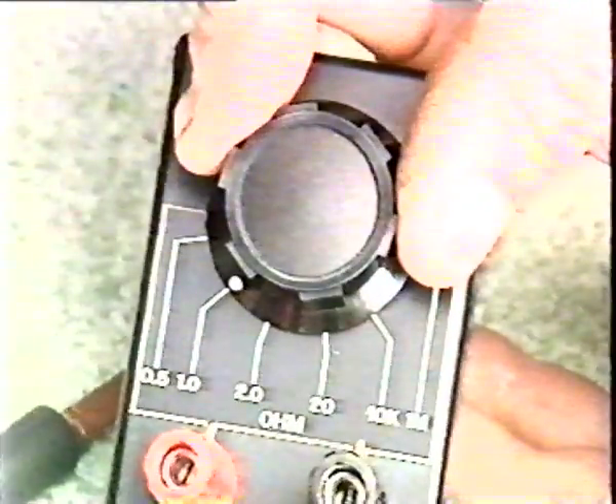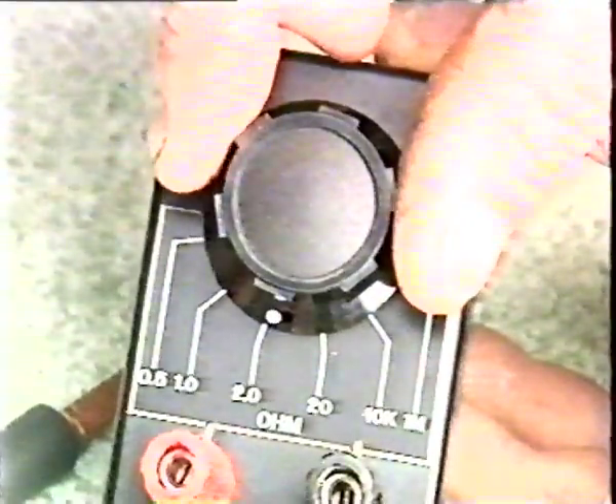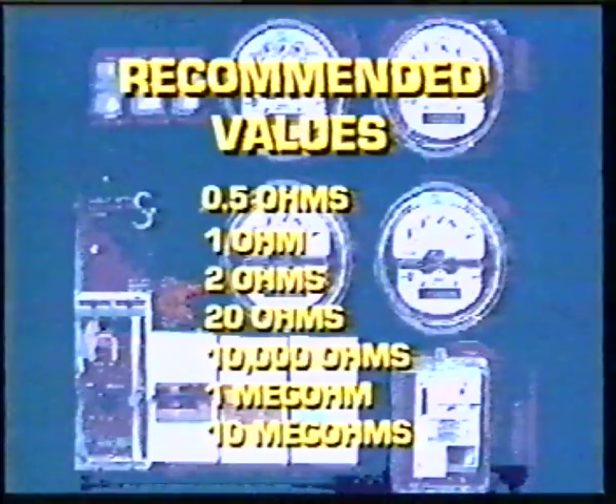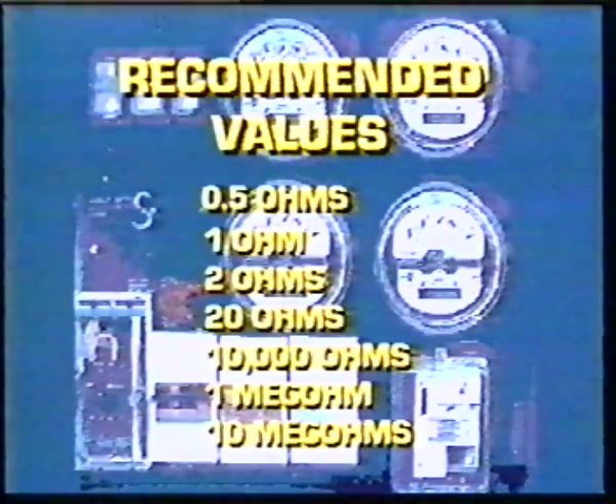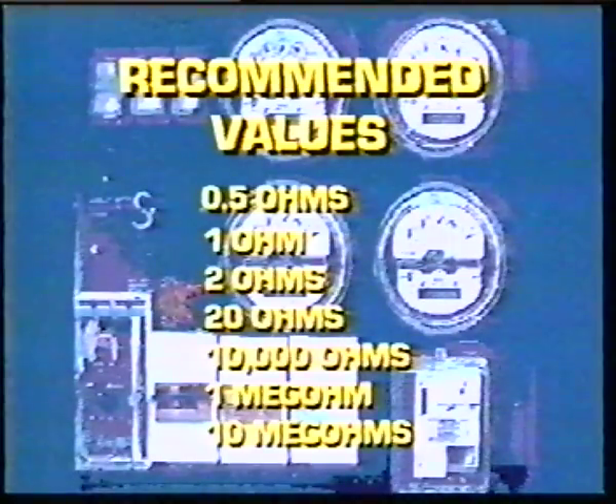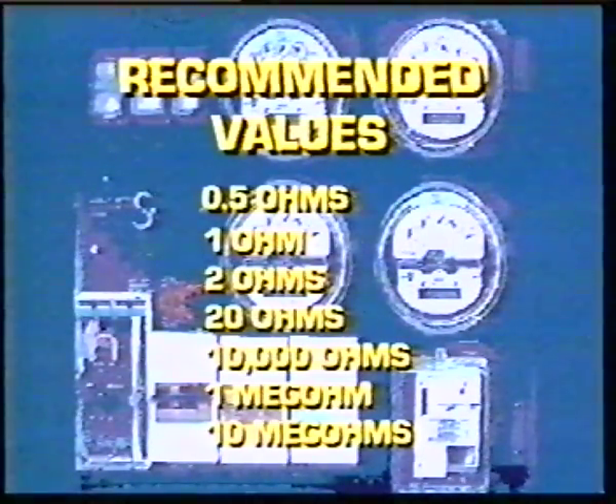In the case of the insulation resistance tester, it must be capable of maintaining its rated output voltage when testing a circuit or equipment with an insulation resistance of 1 megohm. Most modern insulation resistance testers will meet this requirement, but older equipment, such as the hand-wound generator type, should be checked before use. And of course, all testing instruments should be tested for accuracy at regular intervals, particularly after extended storage periods or rough handling. These instruments can be checked against a range of standard resistors having a tolerance of plus or minus 1%. Values of 0.5 ohm, 1 ohm, 2 ohms, 20 ohms, 10,000 ohms, 1 megohm and 10 megohms are recommended.